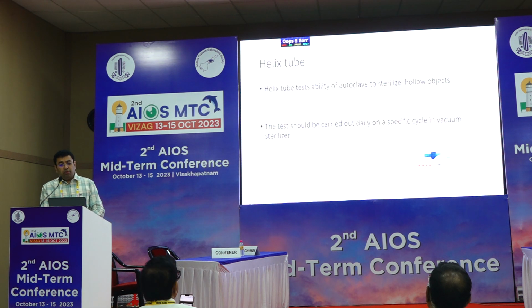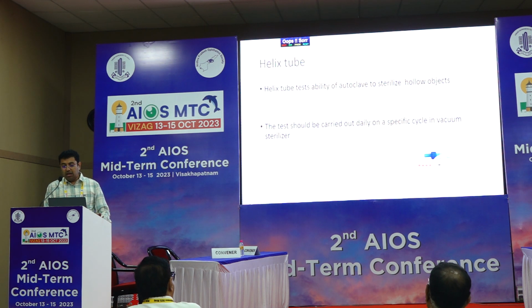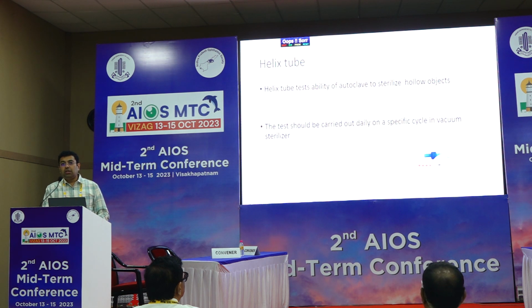Then the helix tube is a specific type of chemical indicator which is used to test your sterilization process of hollow instruments like your phaco tubing. What happens in a helix tube is, if you see, there is a knob here. This is the indicator. The indicator is placed inside the knob here, and once you do a sterilization, the steam goes through this tubing and finally reaches here, and this indicator will change color. So once this indicator changes color, you are sure that the sterilization is complete. This is very useful in hollow tubings, especially your phaco tubings.